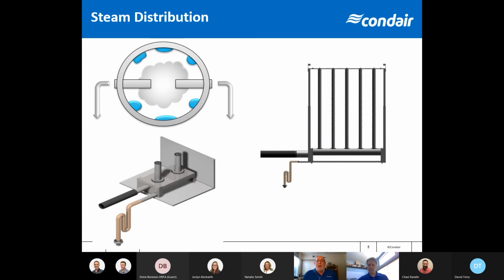And here on this page, we kind of show how it works. As we bring the steam into the manifold, the steam goes up the tubes that are in this grid. In the upper left here, we have a cutaway that shows inside the tube. We have a whole bunch of these little stainless steel tubelets or nozzles so that we're picking up our steam right in the center of the tube. We get a very hot, condensate-free steam.